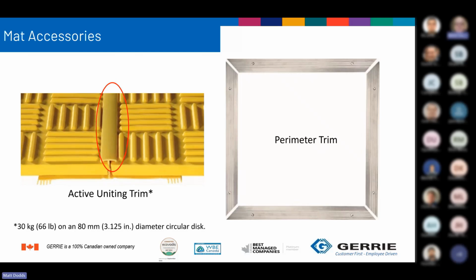The active uniting trim is designed to keep that active surface 100% across the surface. So if you put the test object, an 80 mm round disc, anywhere on that mat, including that active area, it will activate the mat. And all mats need to be held in place, not just laid on the ground, and hopefully nobody will pull them out of the way. So securely fastened with a perimeter trim. Safety mats are designed for machine shutdown, not as a hold to run. If you want the operator to stand on the mat to keep the machine running, no, it's used the other way: if the operator steps on the mat, it stops the machine. It cannot be used in that area.